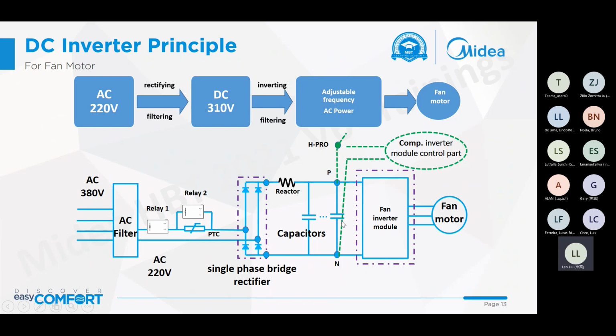This is for fan motor. So the DC voltage goes to the fan inverter module. So similarly, DC voltage is transformed to the adjustable AC power supply for the DC fan motor. So the DC fan motor can be driven by this adjustable voltage here. It's the principle of the fan motor here.